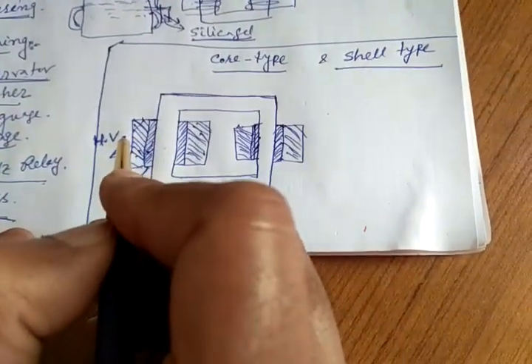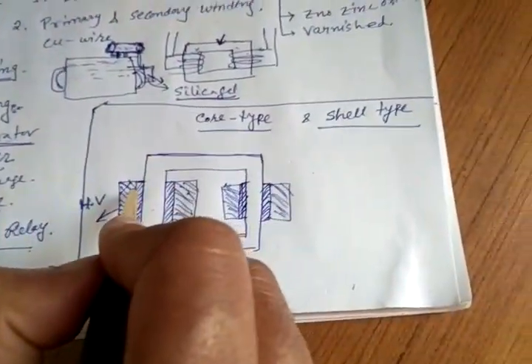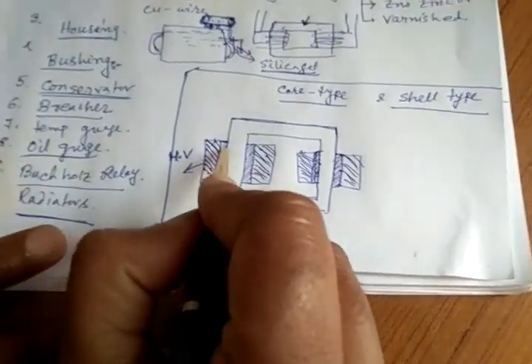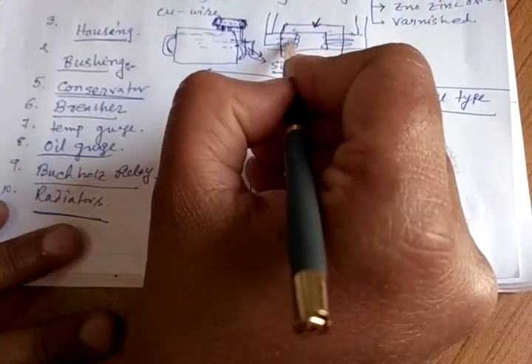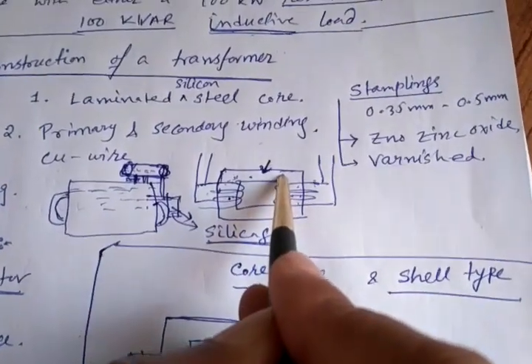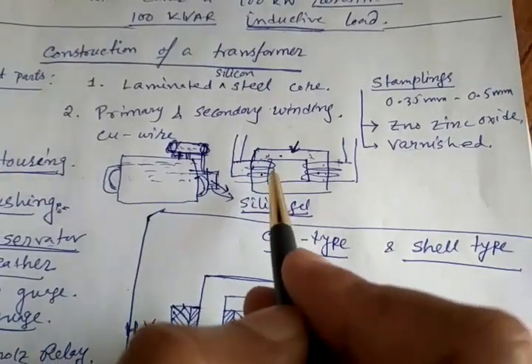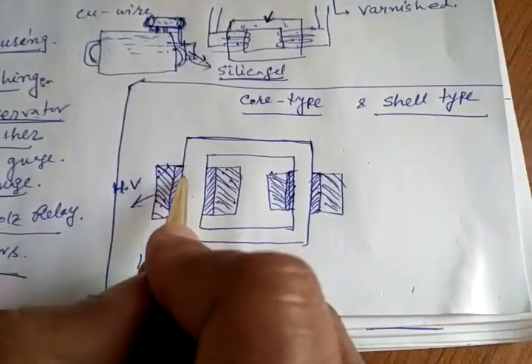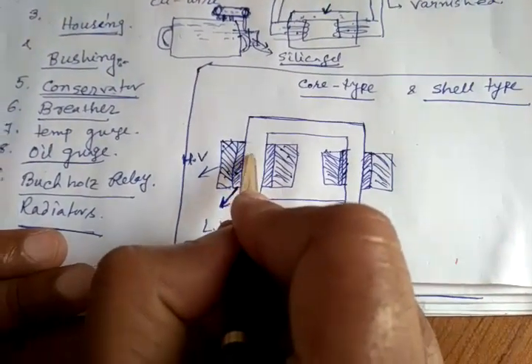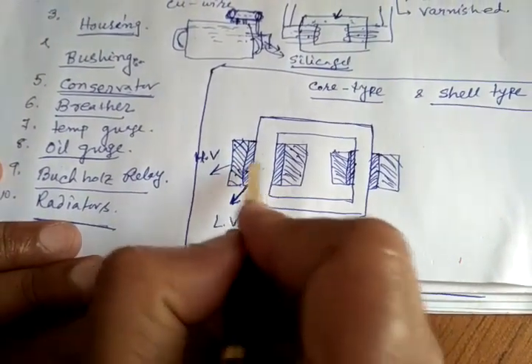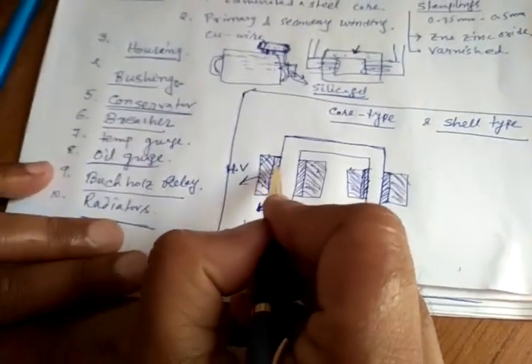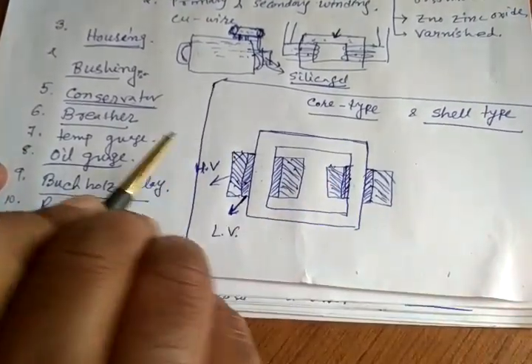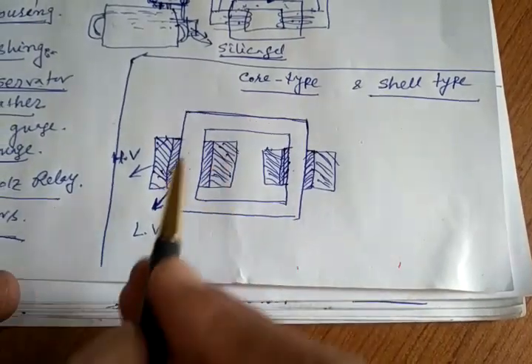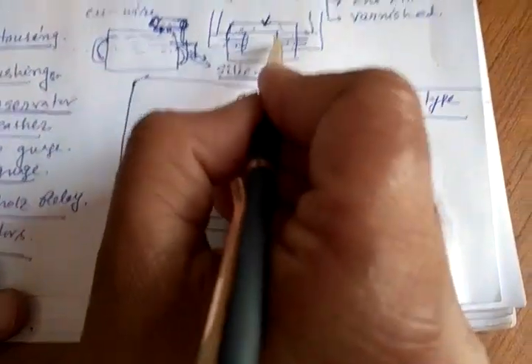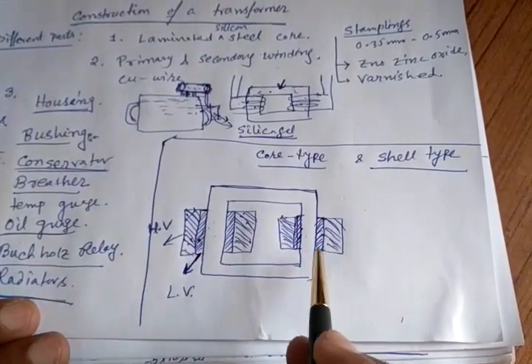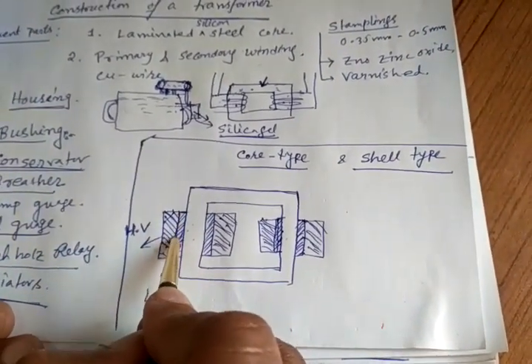So there are certain distinct advantages of this, because if you do it like this, then one important feature is that we have said we need to insulate everything, like insulate the primary coil from the core, and the primary coil from the secondary coil and the core. Everything needs electrical isolation or insulation. Now if this is the low voltage winding, then the insulation required between the core and the low voltage winding will be less. So first we have given the low voltage coil, and less insulation is required. Then once this low voltage winding is done on this side and on this side, we put a very strong insulation, that is, we call it high voltage insulation, to separate the low voltage coil from the high voltage coil, that is the separation between this and this. Then we wind the high voltage coil on both sides. So in this way we can save on insulation cost and insulation requirement.